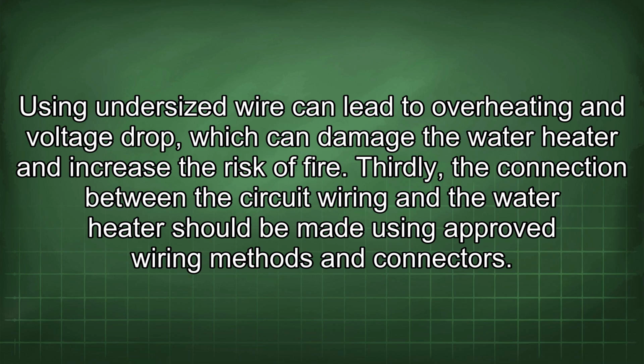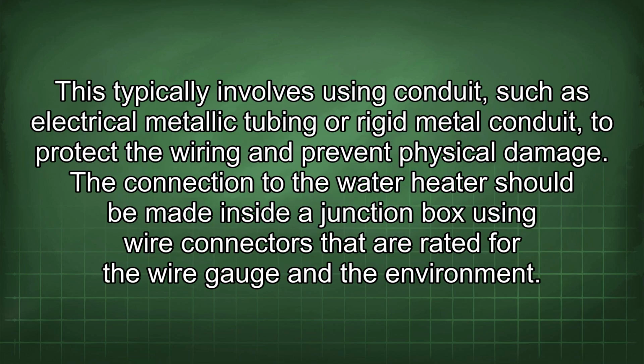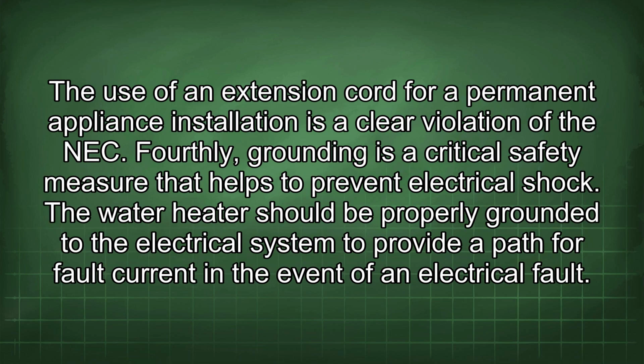of fire. Thirdly, the connection between the circuit wiring and the water heater should be made using approved wiring methods and connectors. This typically involves using conduit, such as electrical metallic tubing or rigid metal conduit, to protect the wiring and prevent physical damage. The connection to the water heater should be made inside a junction box using wire connectors that are rated for the wire gauge and the environment. The use of an extension cord for permanent appliance installation is a clear violation of the NEC.